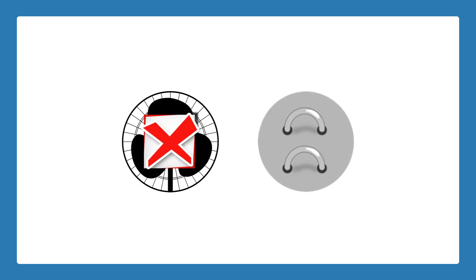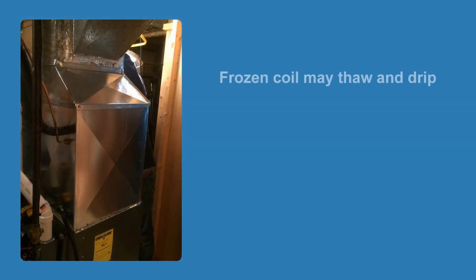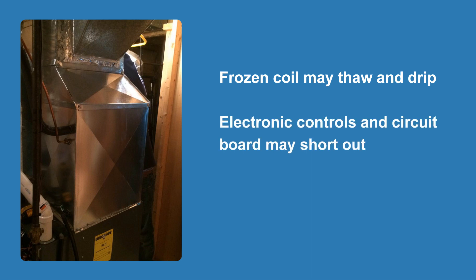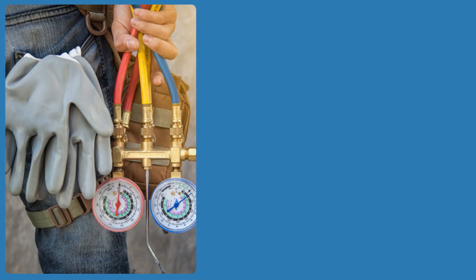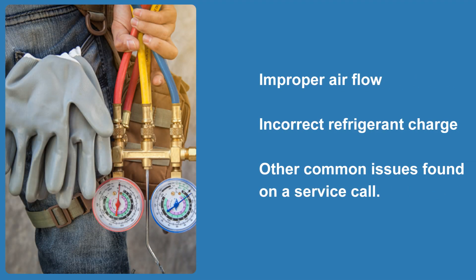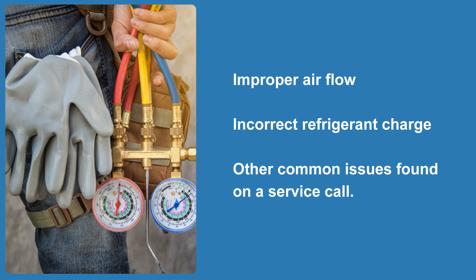If the furnace blower motor stops working, this can result in the air conditioning coil freezing up, which can damage your furnace. Most of today's gas furnaces contain electronic controls and do not like to get wet, so when a frozen coil above the furnace starts to thaw and drip water onto the electronics, the circuit board will usually short out and will need to be replaced. A skilled technician will properly diagnose any issues with your air conditioning systems, such as improper airflow, incorrect refrigerant charge, or any other common issues found on a service call.